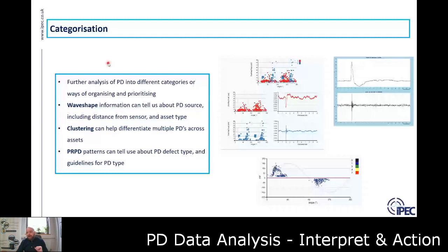There are a few different ways to categorize PD, and the list is actually a bit longer than what's on this slide — these are the key ones. The first is wave shape. We have the ability to look at the individual wave shape, and how the wave shape pattern of PD occurs gives us an indication of where the PD may be relative to the sensor and relative to the asset.